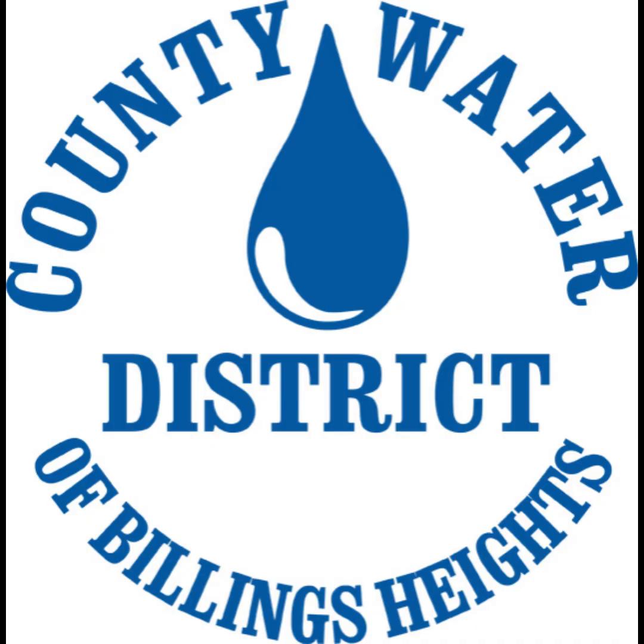So the perspective of the City of Billings is that the risk is pretty low if we have a single check valve. Again, that's what we have at Walter Pump Station. Besides the check valve, there are also interconnections between the City of Billings and the Heights Water District with just gate valves, and those provide less protection than a check valve does. So, again, it's not my decision.